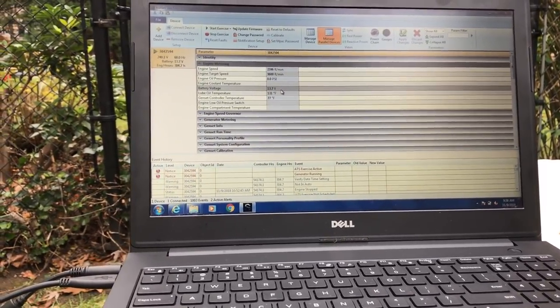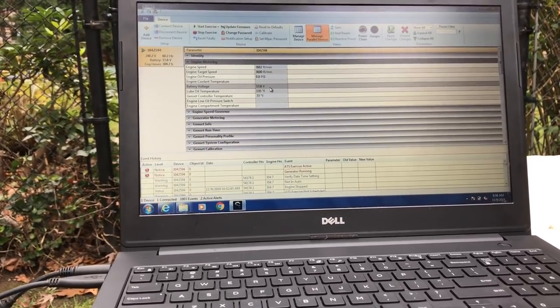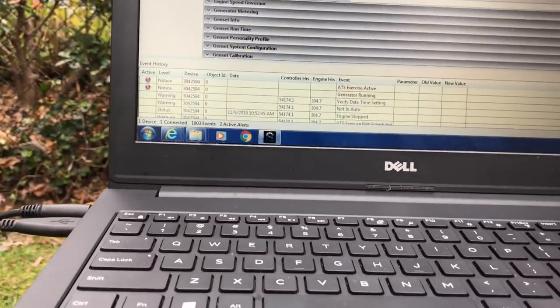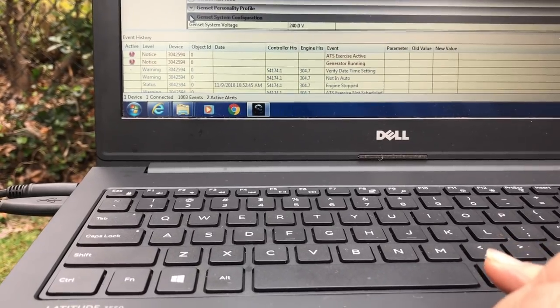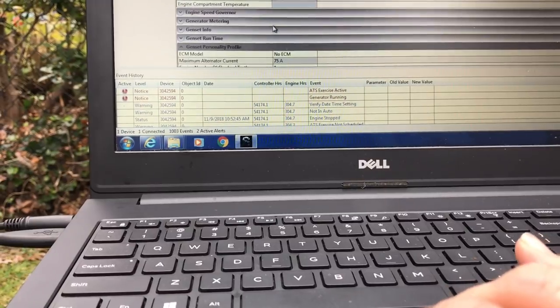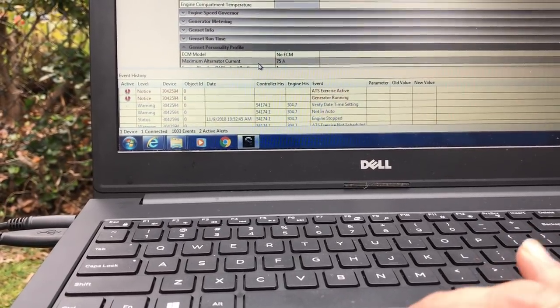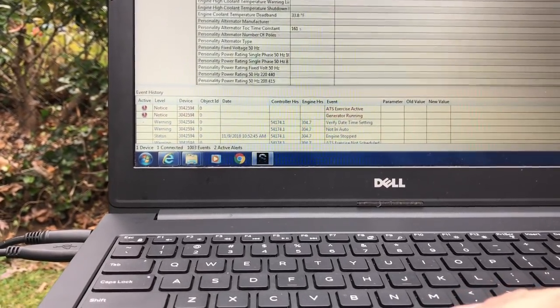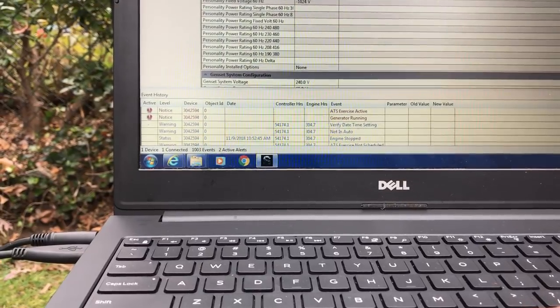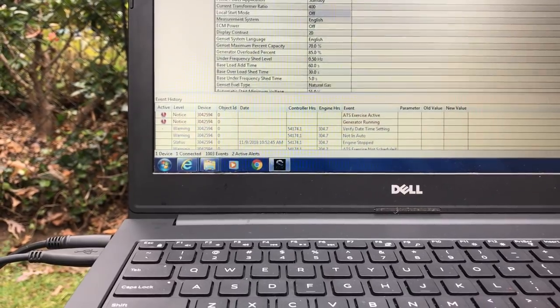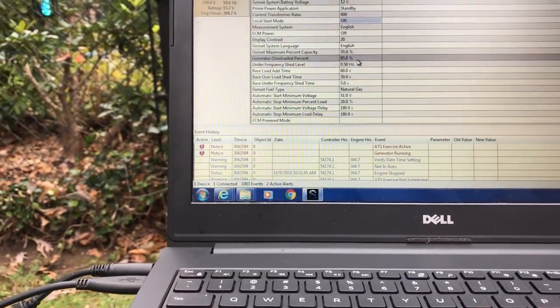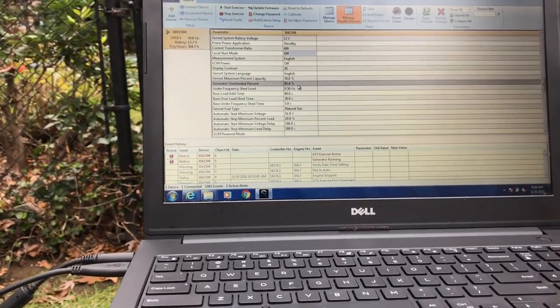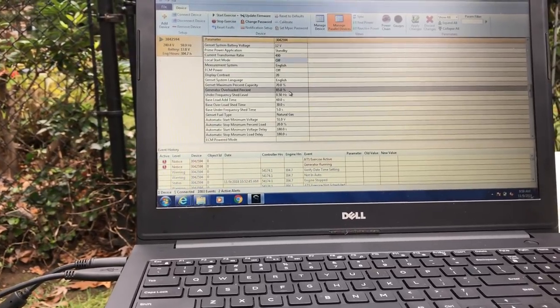This just shows you a little bit more on how this controller interface works with the generator, and as we make adjustments to many different things, I can change the voltage output, I can change where it shuts down. All the safeties I can make changes to even though I don't want to. I can change the maximum capacity, the overload. I can make changes to these things, but the manufacturer wants it a certain way, they have a reason why they set it that way for this machine.